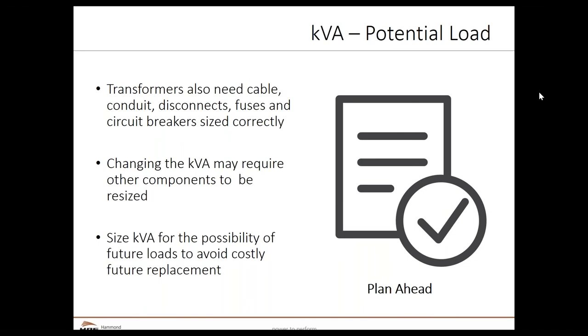A transformer is a component in the distribution system. In this system, there are cables, conduits, circuit breakers, etc. that need to be sized correctly. If you change the kVA of the transformer, you would need to resize the other components in the distribution system as well. It is important that while sizing the transformer, we take into consideration the possibility of future load expansions. This way, you can avoid costly future replacement — plan ahead.